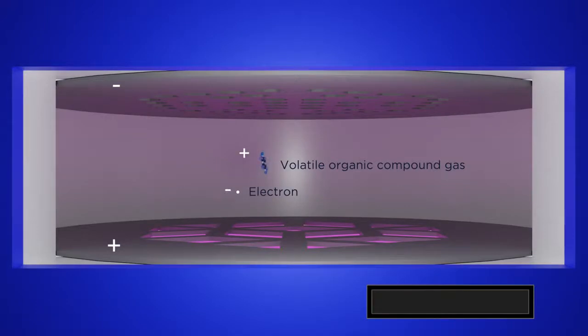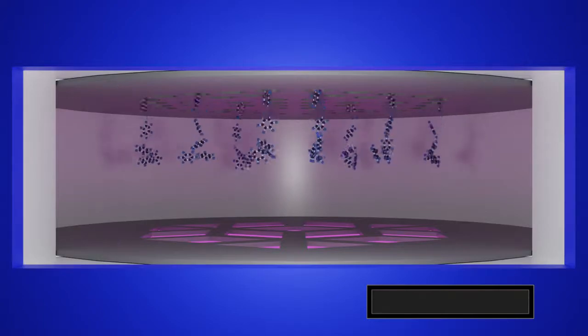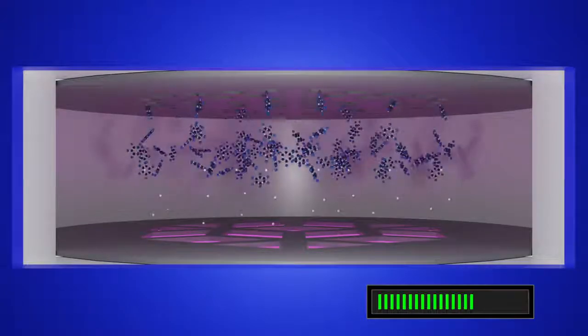The negatively charged electron is attracted to the positively charged electrode. The positively charged molecules are then attracted to the negative electrode. This creates a tiny current which is then amplified. The signal increases and decreases with the VOC gas concentration.